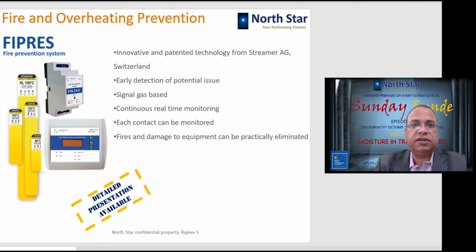Okay, so this is not a transformer thing. It is for control panels, power panels. It is a fire prevention system which is useful in panels where, because of loose contact or overheating, the fire sets in, and as a result a big loss happens. So this is a unique system which monitors every joint in your power panels or control panels, and you get an alarm much before the actual danger is going to start.